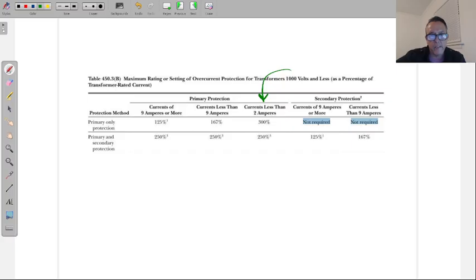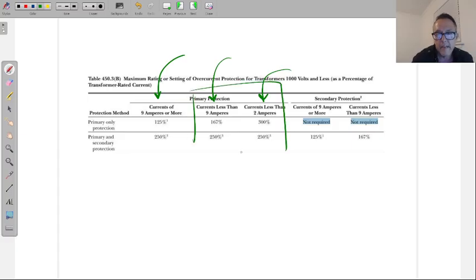All right, those control circuits, like motor control, lighting, and traffic signal control, they are using low voltage. So they're really worried about getting 12 volts to all their components. A little bit larger lighting systems. Really, this is the lighting system world. A little bit bigger, but less than 9 amps. So whatever you're operating is less than 9 amps. A bunch of lights for warehouses and things of that nature. And now the large ones, really for anything else above 9 amps. You'll notice this is a very odd separation of amperage in the code book. Right, some weird numbers to go with, but it is the transformer world.